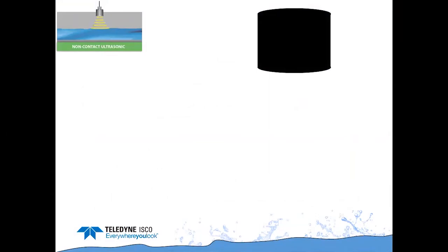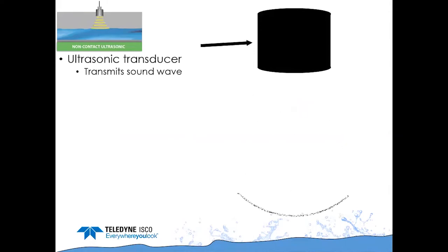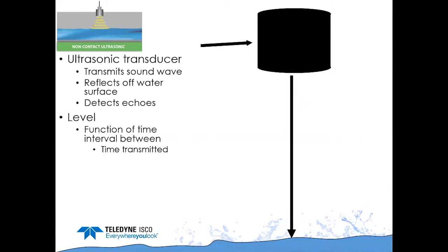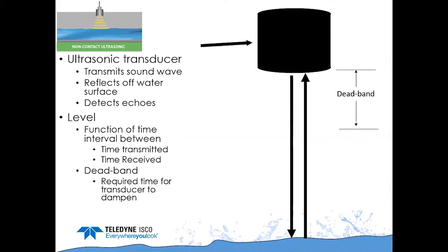An ultrasonic sensor is a non-contact sensor mounted above the flow stream. It transmits a sound wave which reflects off the water surface and detects the echo. The time it takes to transmit and receive the signal determines the distance to the water surface, which is calculated into a level. All ultrasonic sensors have a deadband — the time the transducer needs to dampen after transmitting before it can receive — ranging commonly from two inches up to two feet.